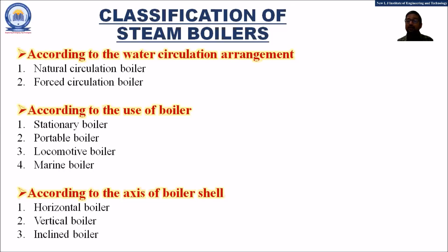But friends, considering the mechanical design and the loading conditions, right now people are not preferring the inclined boiler. Because if you think technically, apply your engineering mindset, then if the boiler is inclined and high pressurized steam is generated, tremendous support structures need to be provided with the boiler. And if any one or two of the supports are broken in any case, it can result in a very big accident. So considering all these concepts, people have now restricted using inclined boilers. They are only targeting the use of the horizontal boiler or the vertical boiler.